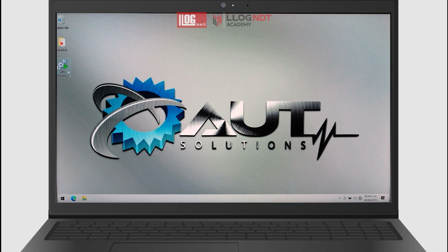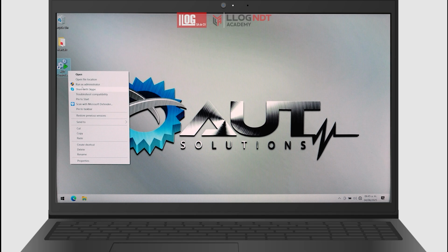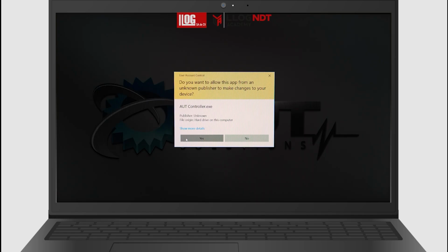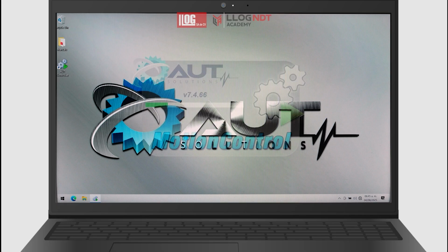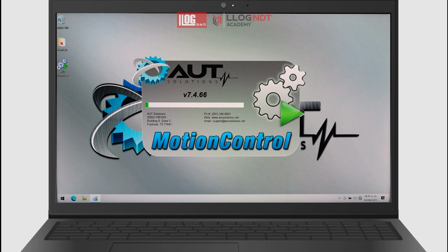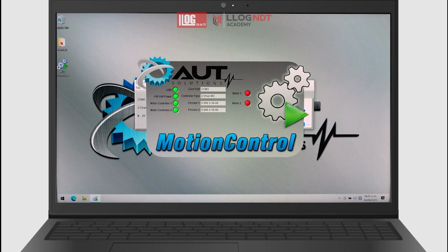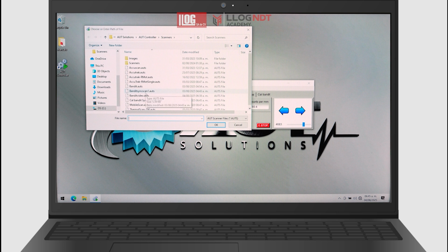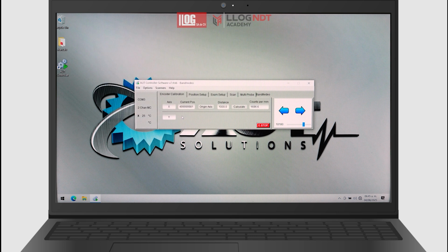To begin the encoder configuration, run the AUT Controller software as administrator. Once the software starts, verify the connections of the controller, the encoder, and the SyncScan 3 unit. When the status indicators turn green, press Continue. In the File menu, select the encoder configuration. For this example, select the Bandit model. Confirm the selection, and the software will automatically calculate the pulses per millimeter. Now we can begin the encoder standardization.